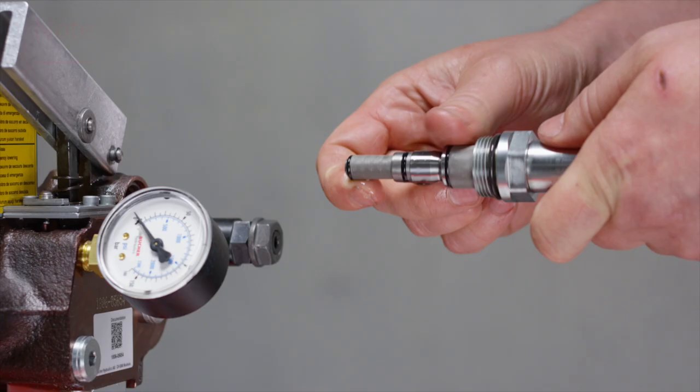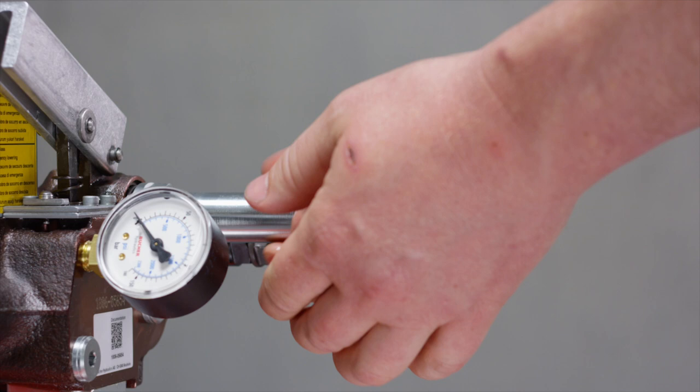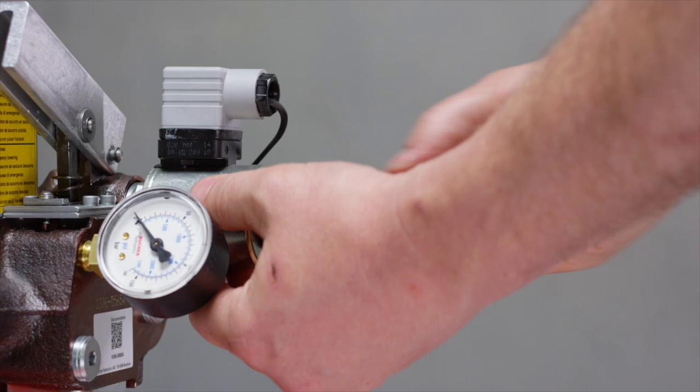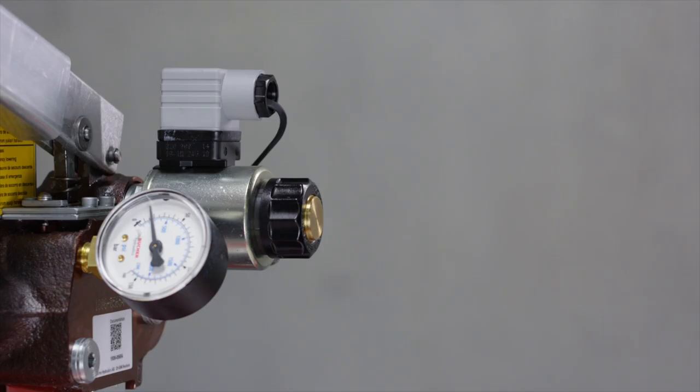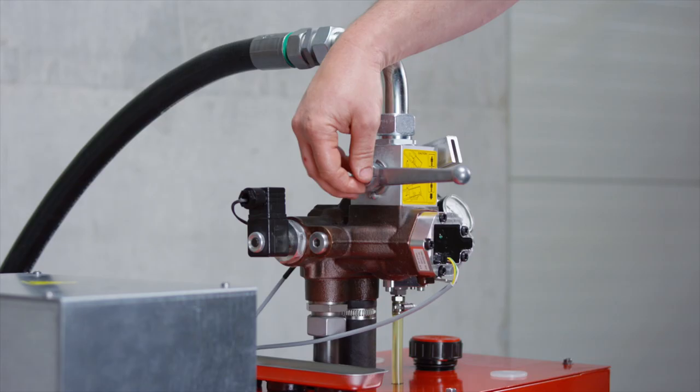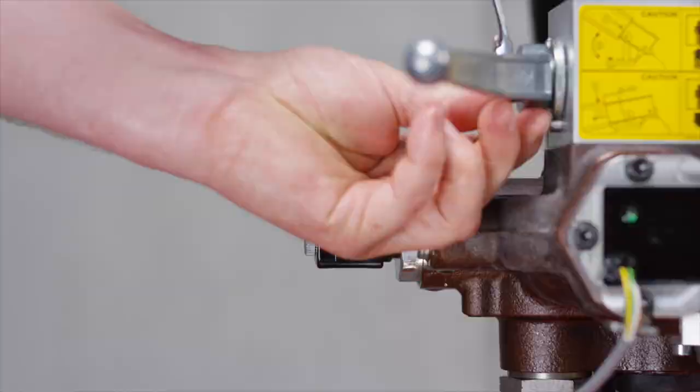Reinstall the pilot valve, including solenoid coil, in the starting position. Build up pressure with hand pump at the lift control valve to check it for leakage. Install the lever and open the ball valve.